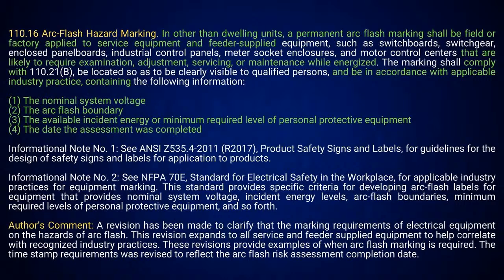You need to know the clearing time of the overcurrent device and the distance. Now, once you've got those three, then you can start making assumptions. Well, hey, spoiler alert, the distance is not the working clearance. I'm not going to go into every bit of that because it takes too long. But the typical is 18 inches, that's basically your arm length. Okay, that's put in the calculation.